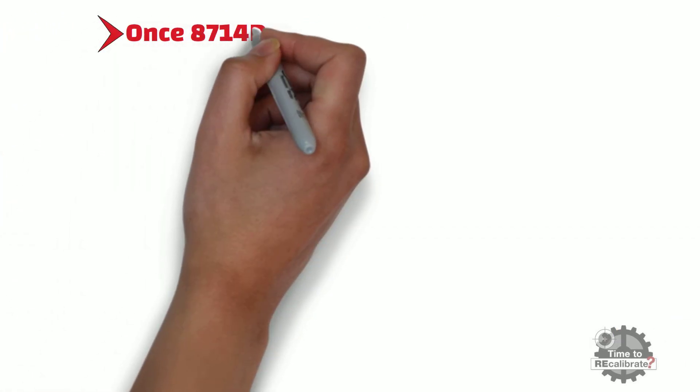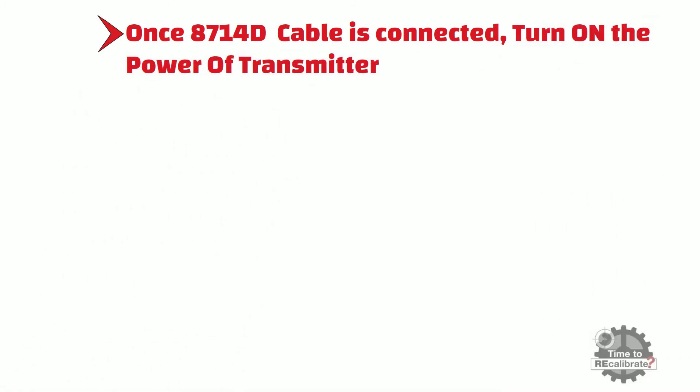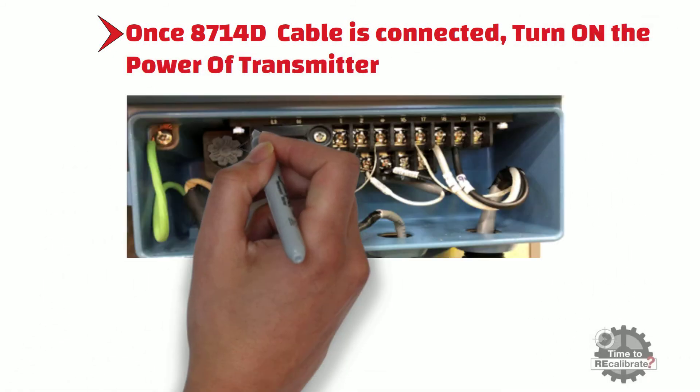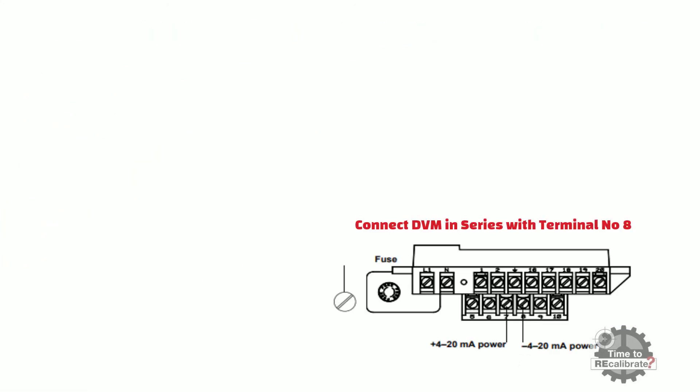Step 7: Once the cable is connected to the transmitter and simulator, turn on the power of the transmitter. To power up, push the power fuse gently inside and rotate in the clockwise direction. Now disconnect terminal number 8 and connect a digital voltmeter in series with this terminal to measure the milliampere output reading of the transmitter. At this stage, everything is set up and we are ready to perform the verification test.